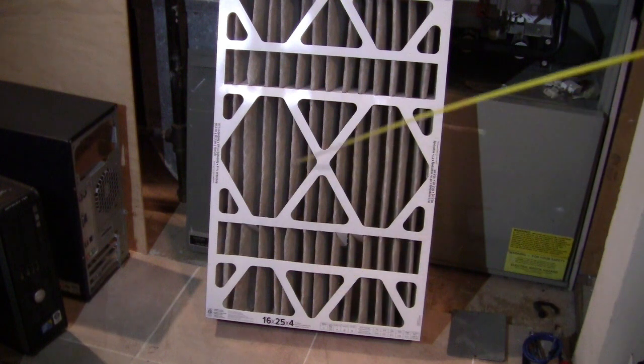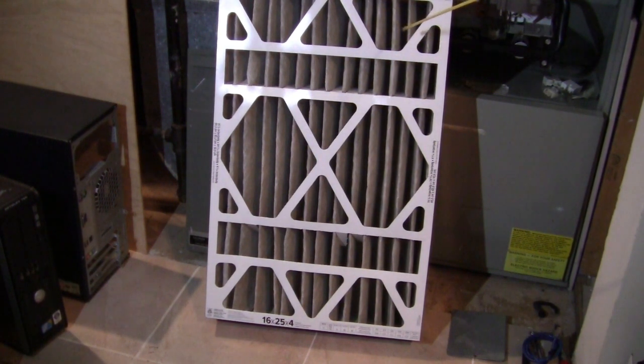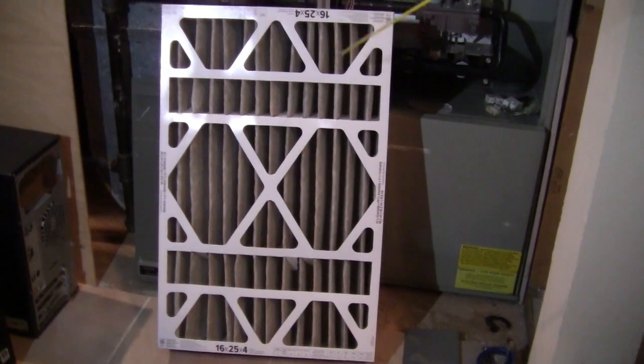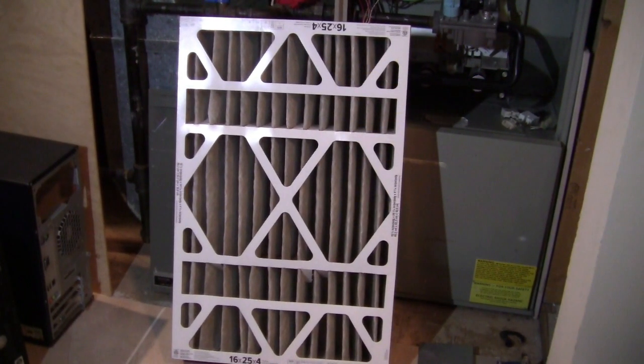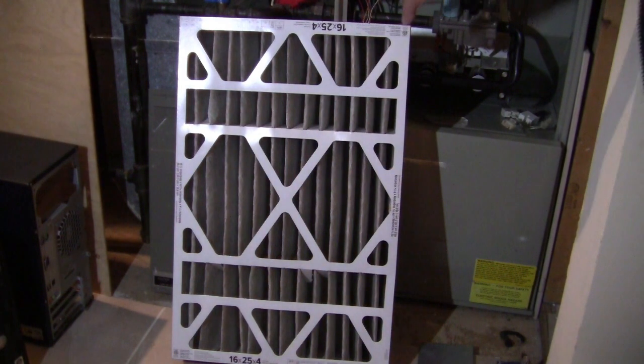If you leave this thing for years, not changing it, and it gets very dirty, the holes inside the filter get sealed, so the air won't be able to pass through. Without the air passing through, the air will not be able to circulate to the house. So this thing can actually block the air from the inlet to the outlet. So this is the easiest fix, the first thing we need to do for our maintenance work. Also, regarding the filter, there are a couple of things we need to know. First thing is there is an arrow over here.